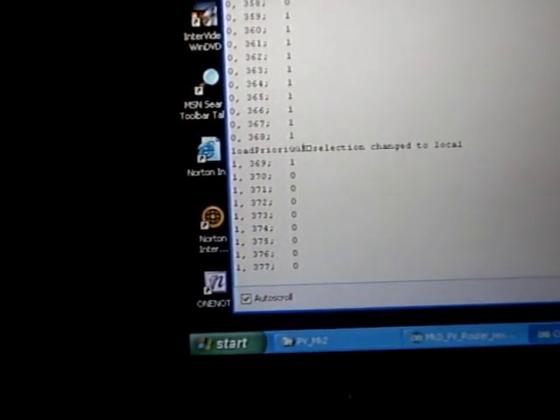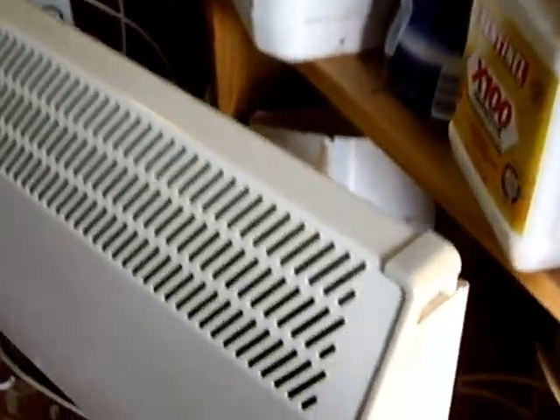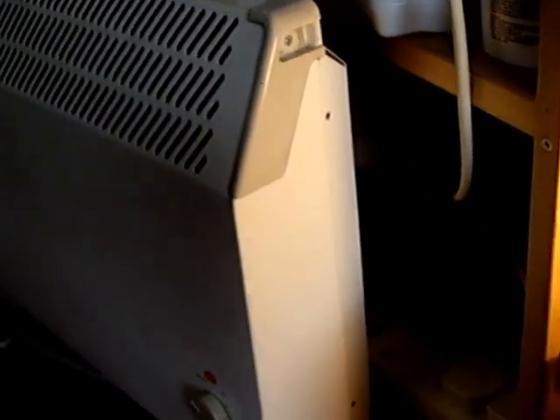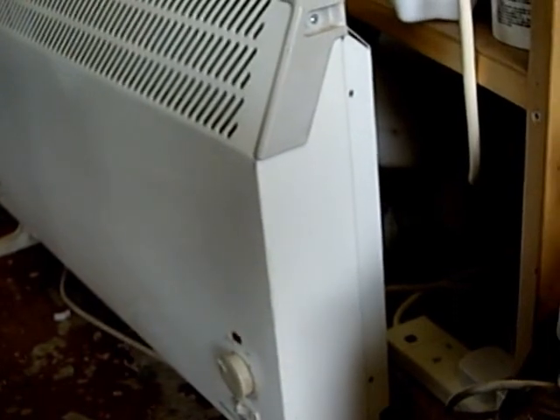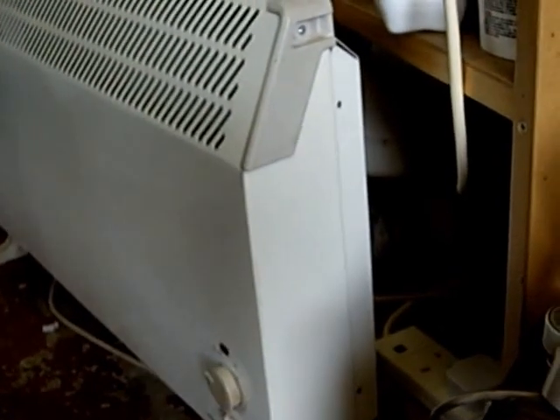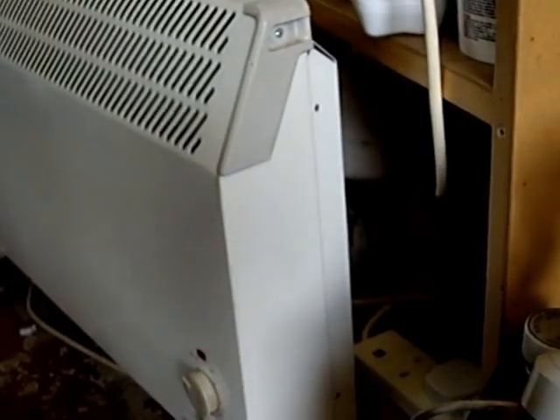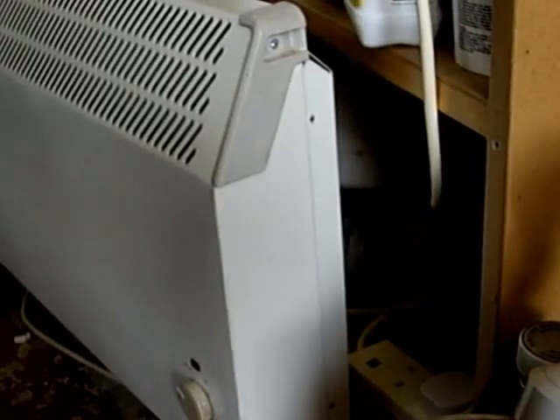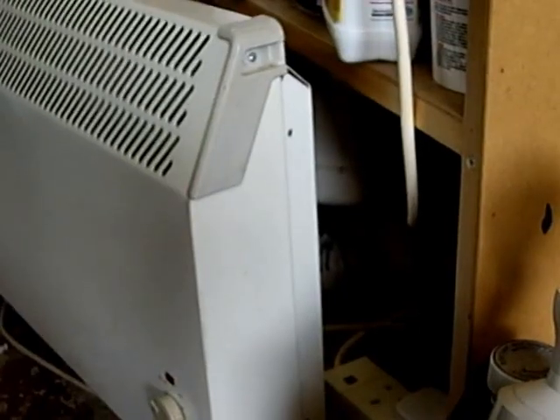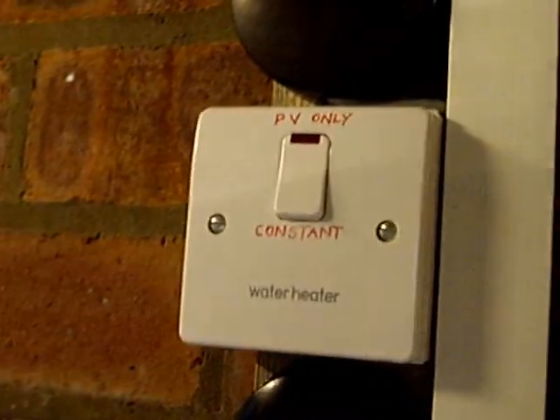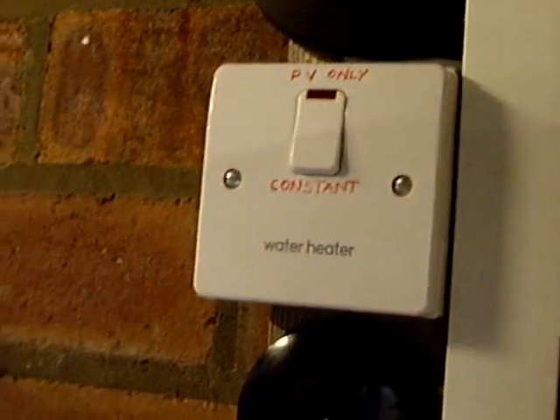So, putting remote on to priority, which is probably more interesting, so we get the light on. If I now put my fire on, that's a 1 kilowatt. This is as we were before, so we've got 1,060 watts of dump load on remote, so this should be flicking on and off at roughly 2 to 1, and we should get nothing up here, because this is a secondary priority, and we're still getting our 750 there.